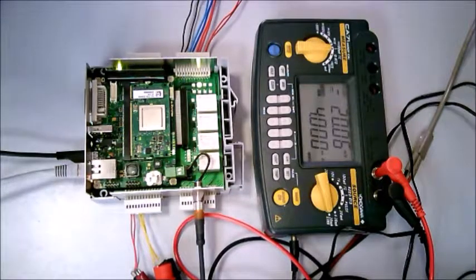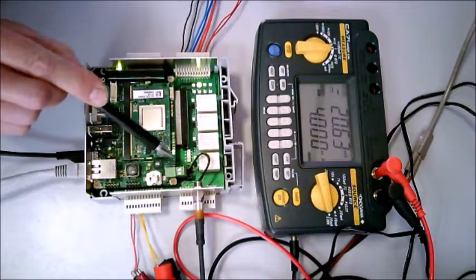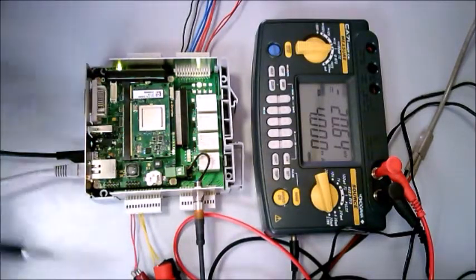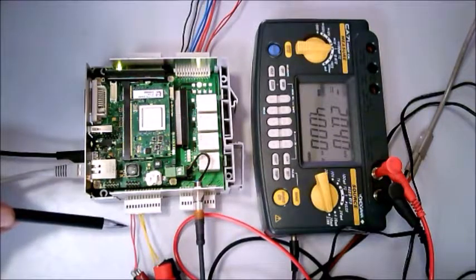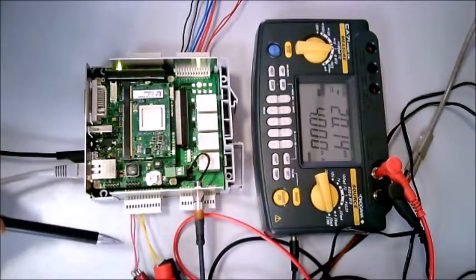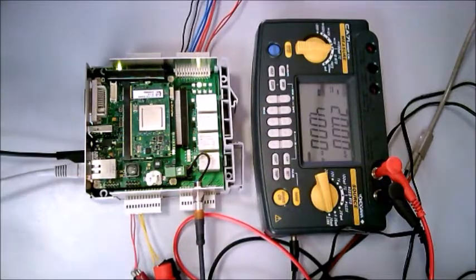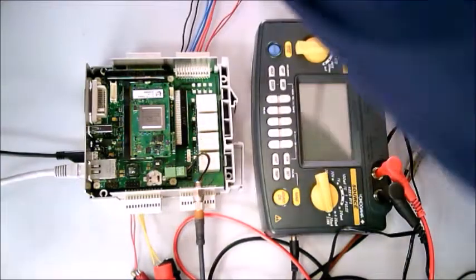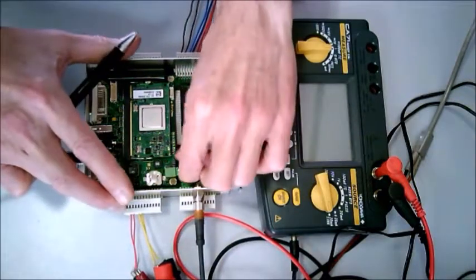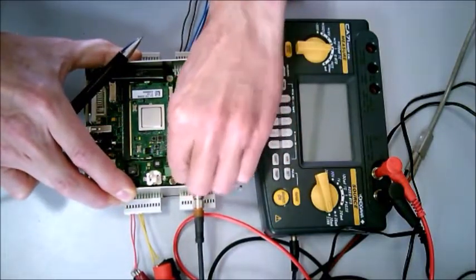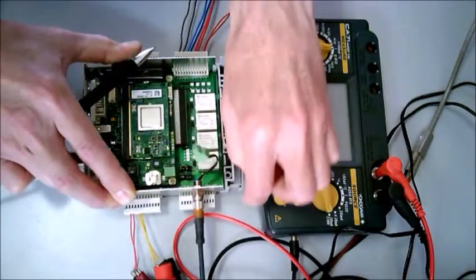Okay, the first thing we have to do before starting the testing and calibration utility is to adjust the jumpers to configure if the hardware will accept an active or a passive connection. So to do this we have to switch off the unit and we have to remove the power supply connector of the carrier board.